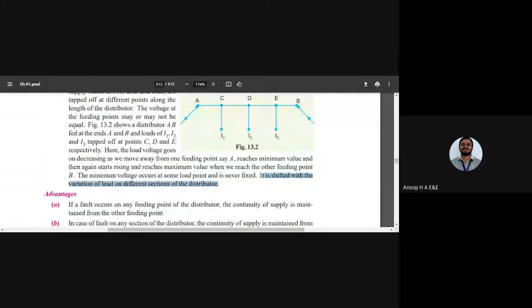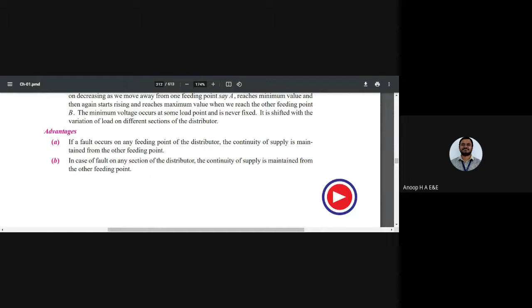Feeder here means where the feeding is done to point B of the distributor network. That is where we observe it reaching a minimum and then going to a maximum value. The minimum voltage occurs at some point of the load and it is never fixed. It shifts with the variation of the load in the different sections of the distributor. That is the reason it is called a distributor fed at both ends. As I told you previously, there are certain advantages when you feed a distributor from two ends. In case of a fault condition, it has continuity of supply. The continuity of the supply is not missed in any of the sections of the distributor.